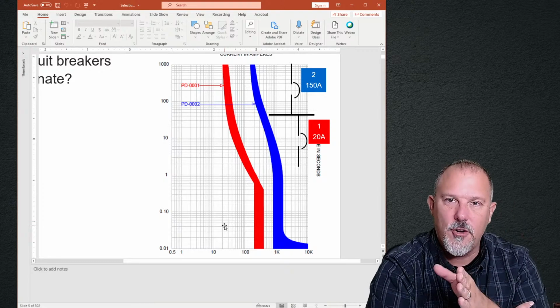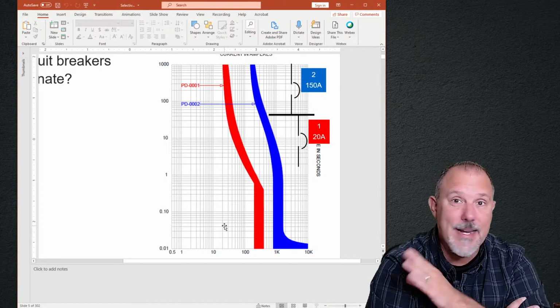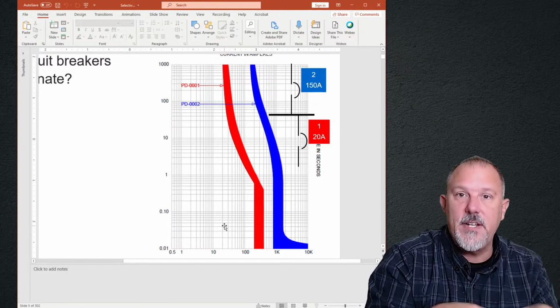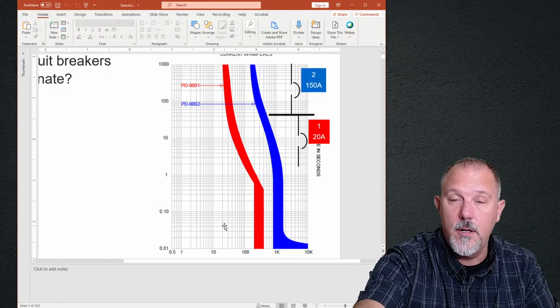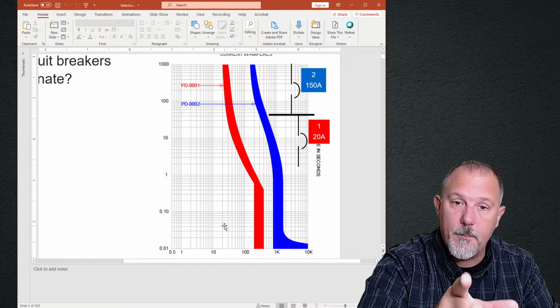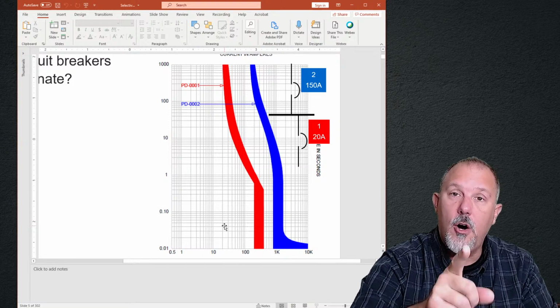Because I don't know the fault current. If the fault current is 10,000 amps, I can tell you they don't, because of the definition and because I know what the goals are: to isolate the fault current. That 20 amp breaker should be the only one that opens on those fault currents.